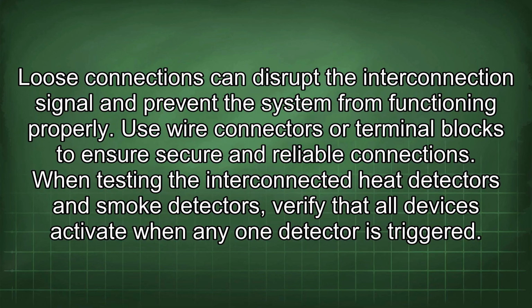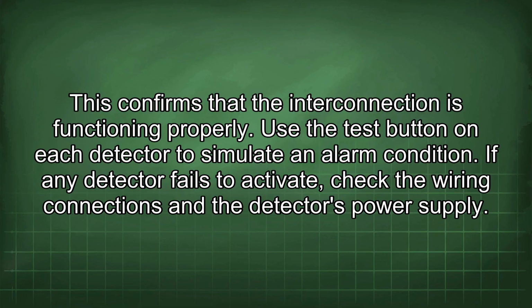When testing the interconnected heat detectors and smoke detectors, verify that all devices activate when any one detector is triggered. This confirms that the interconnection is functioning properly. Use the test button on each detector to simulate an alarm condition. If any detector fails to activate, check the wiring connections and the detector's power supply.